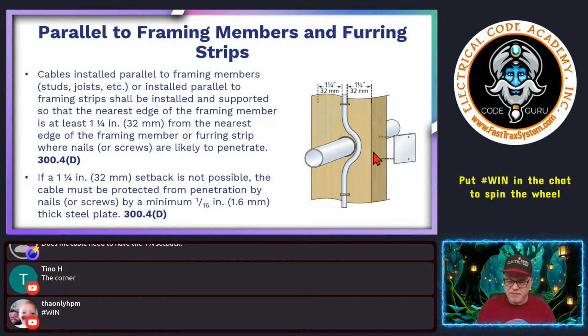Make sense? All right. Now, when you're doing furring strips and you're running it down, you might have to run it off the furring strip because you won't be able to keep that 1 1/4 to the cable. So you might have to run it off the furring strip 1 1/4 and run it down. You might even have to secure it to the block wall if your furring strips are on a block wall, in order to keep it 1 1/4 away.